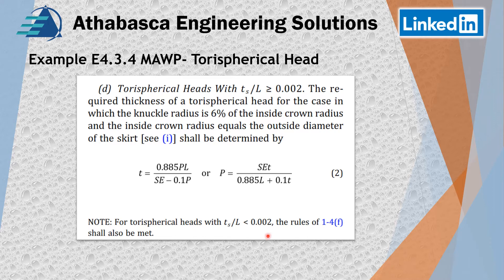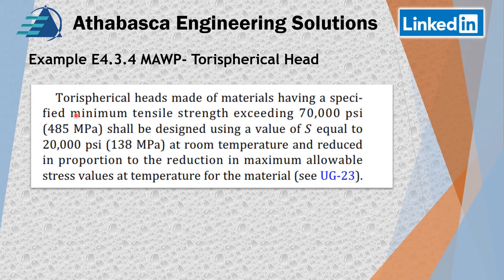If this condition cannot be met, then you can go to Appendix 1-4F. The ASME example in PTB-4 doesn't really go through this, so I built this into our spreadsheet so that we can do a check. They say if you have high tensile strength materials — which is 70 KSI, which you rarely see — but if you're using those materials, then you equate that to 20,000 PSI at room temperature, in proportion to the allowable maximum stresses in the material. That's the setup for that.